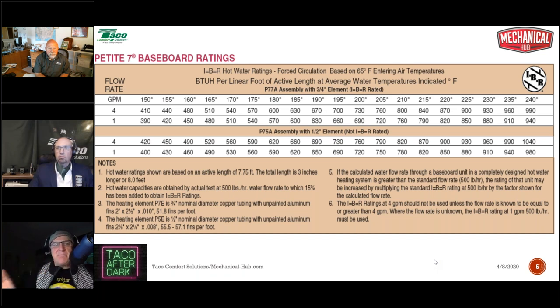Well, okay, depending upon the brand of baseboard you're looking at, that 500 or 550 number may or may not be accurate. When we talk about supply water temperature, all too often, if someone's looking at a chart like this, they're going to say, okay, what's my output at 180 degrees? And what they'll do is they'll look right here, 180 degrees, and they'll see an output of either 600 BTUs per foot or 570 BTUs per foot, whether my flow rate is 4 gallons per minute or 1 gallon per minute through that baseboard. Huh, well, which one do I use? Well, if your supply water temperature is 180 degrees, I would submit to you that you would use neither, all right?